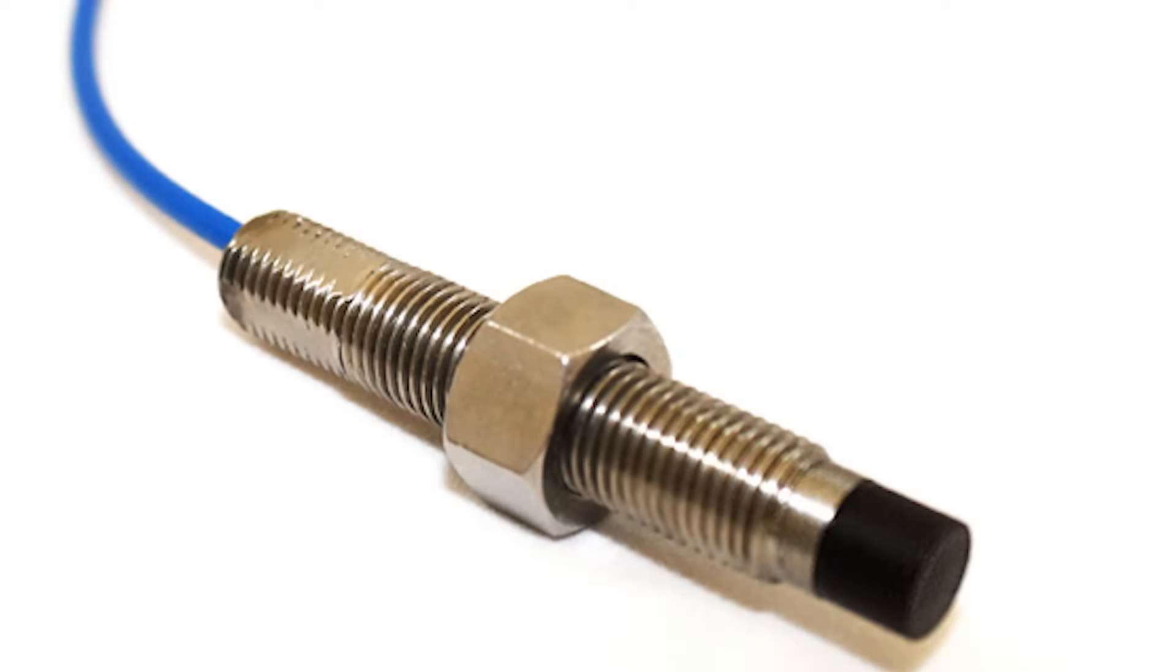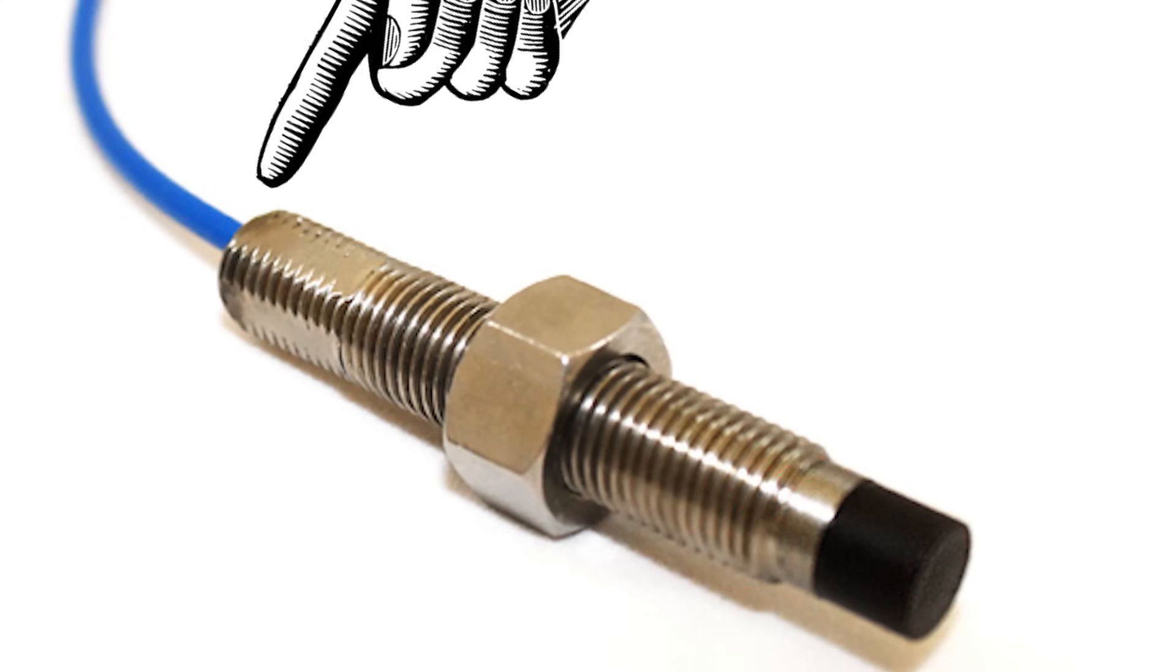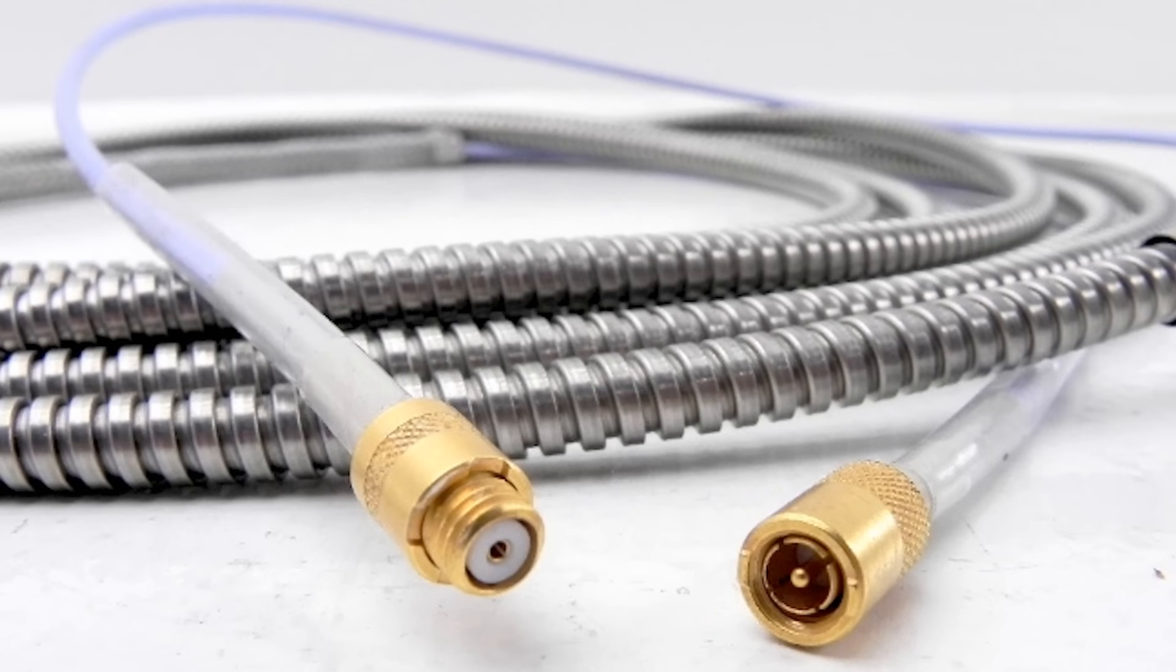The basic proximity probe consists of a pancake coil encased in a non-conductive protective layer. The coil is mounted on the end of a threaded rod. A special coax extension cable is typically used to connect the coil to a proximitor.